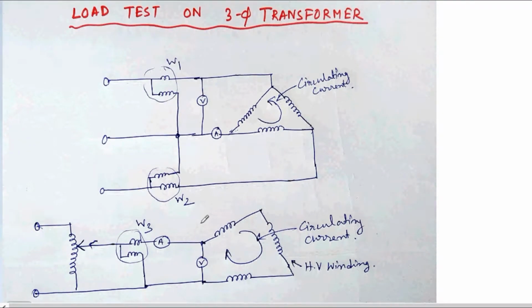And this is the circuit diagram for the load test. In this test, the primary and secondary windings are connected in delta, where the secondary is an open delta connection, and a voltage regulator is used here in the secondary. This is the voltage regulator, from which we can provide voltage to the secondary to circulate the secondary current, and it can be adjusted till the rated secondary current flows through the winding.